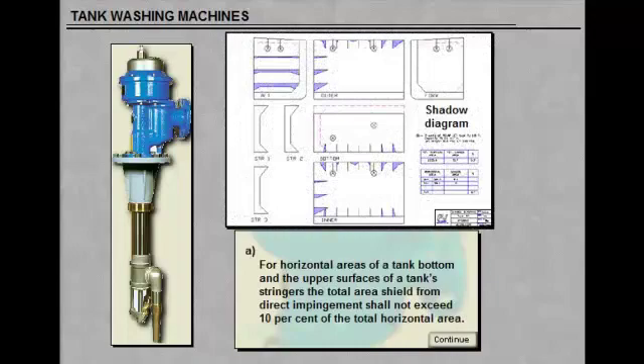For horizontal areas of a tank bottom and the upper surfaces of a tank stringers, the total area shielded from direct impingement shall not exceed 10% of the total horizontal area.